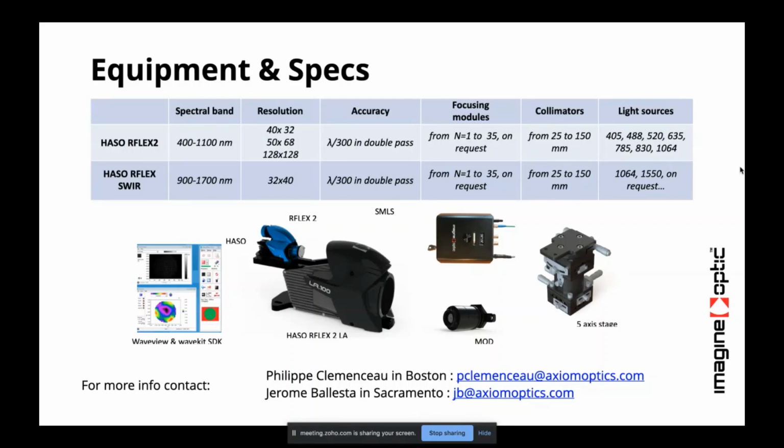You're right. The display we see in the wave view remains on the wavefront sensor side, which means that we do not take into account the magnification created by the focal system, consisting of the modules and the large lens. We discussed this a lot while we specified the software. In our point of view, it's the best way to avoid allowing our customer to make huge errors while interpreting the measurement.